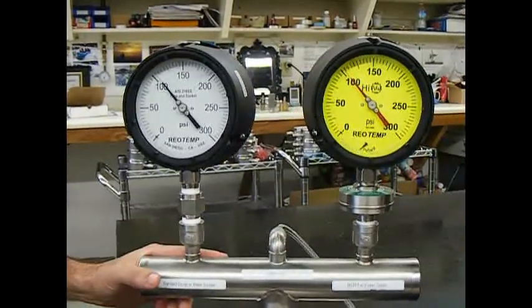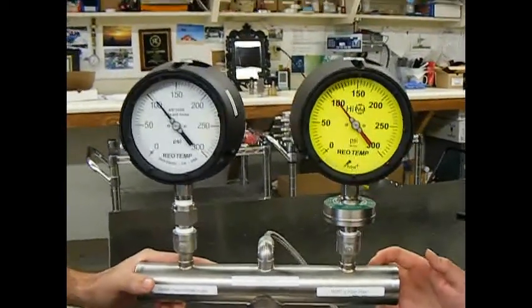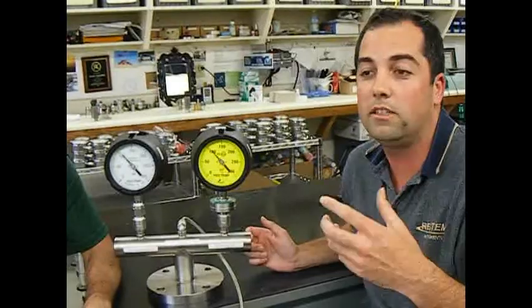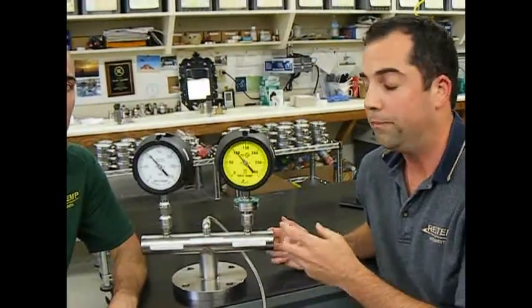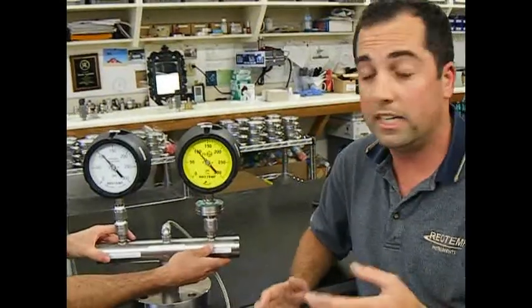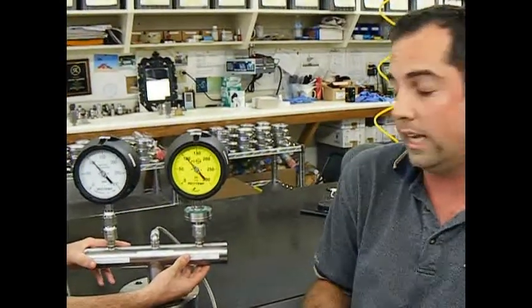On the left here, this is not just a plain diaphragm seal. We've actually embedded a proprietary mechanism inside the gauge above the diaphragm in order to fully slow the process to the point where it's not damaging the gauge. What you saw on the outside here was the final effects of pulsation, the pointer fluttering significantly, and you saw that more so in the gauge on the right.